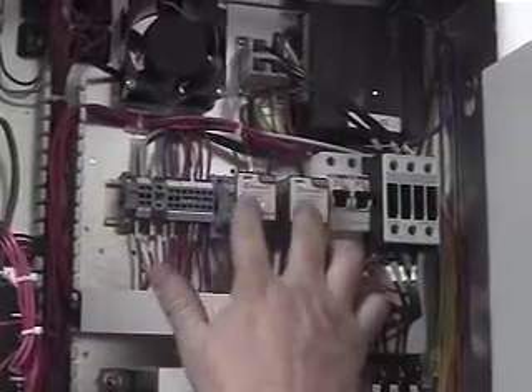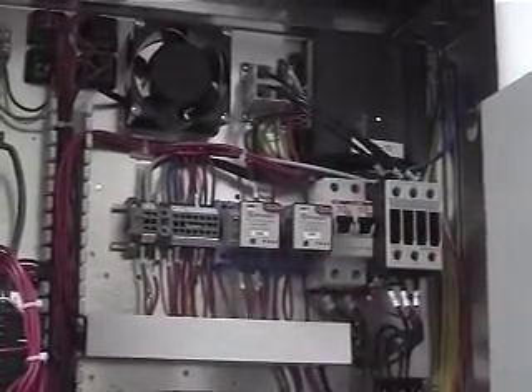We have our contactor for the fan. We also have a relay for the fan. We have a contactor for the heaters. Unfortunately on this one, on the heaters, it's all or nothing. Because it's electric heaters, there's not a modulation or anything we can give it. You either produce some humidity or you're not.